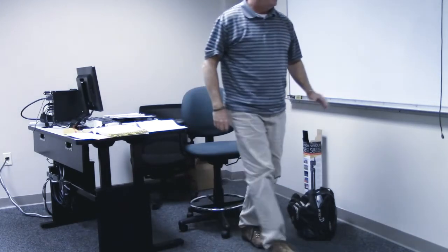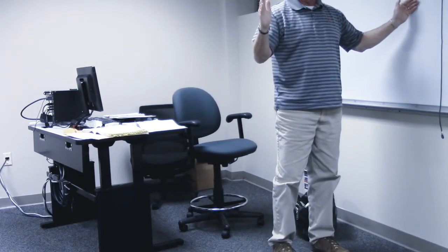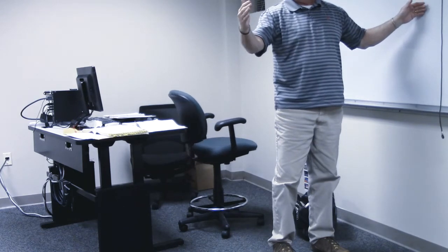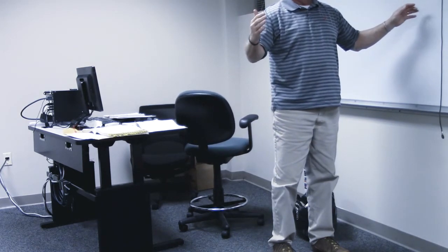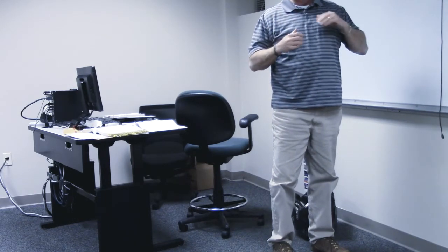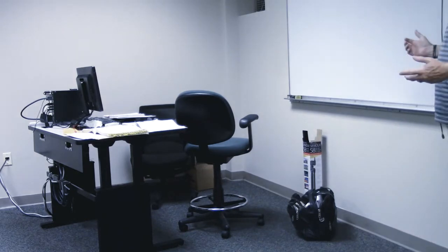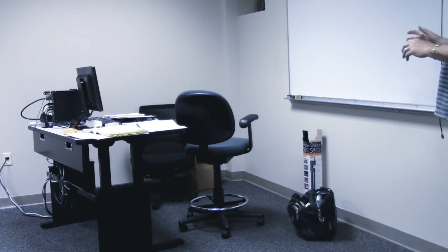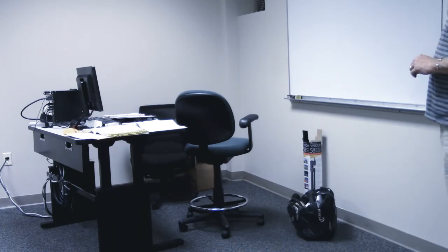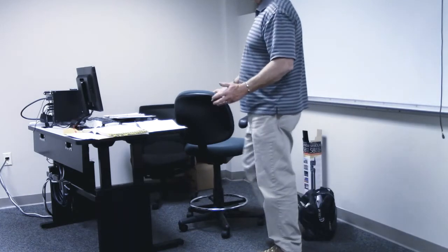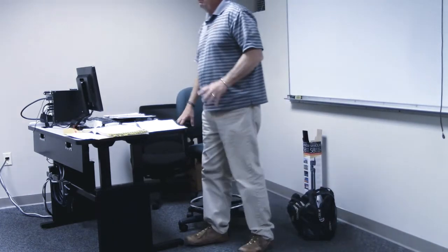Most of the time what ends up happening in an X-ray room is you may have a partial wall here, and possibly a window. And the operator's typically on this side, and that's typically where that disconnecting means is also readily accessible. Because they don't want to be in the room, they're usually looking through a window. And if I remember right, I think the disconnecting means is typically mounted right there. So readily accessible, yeah. And X-ray equipment's usually like a 100 amp load, something of that nature, so it's a pretty large load.